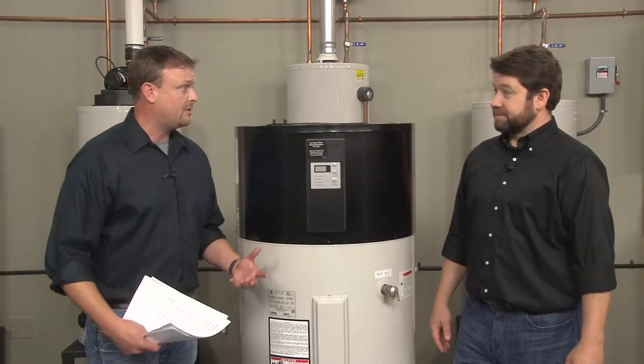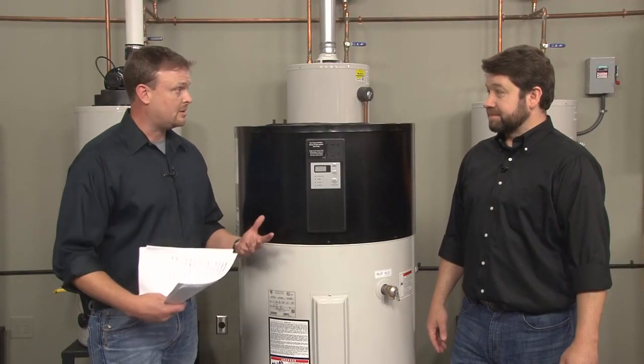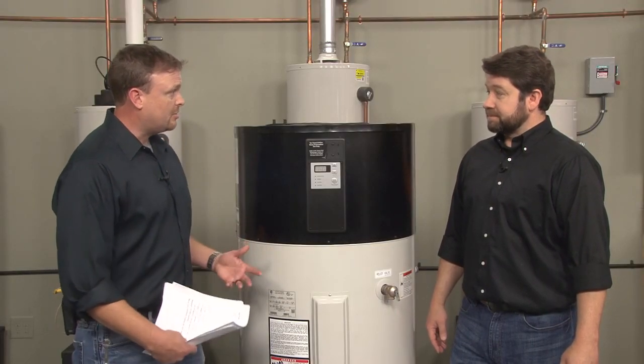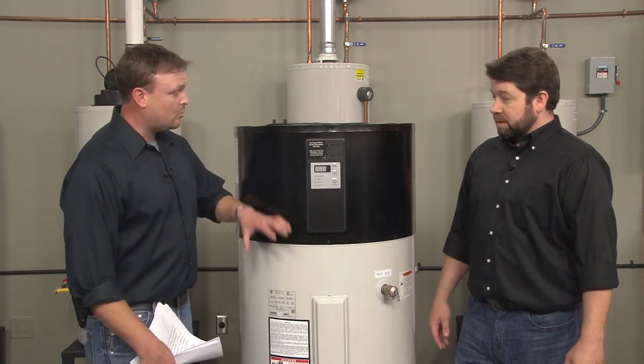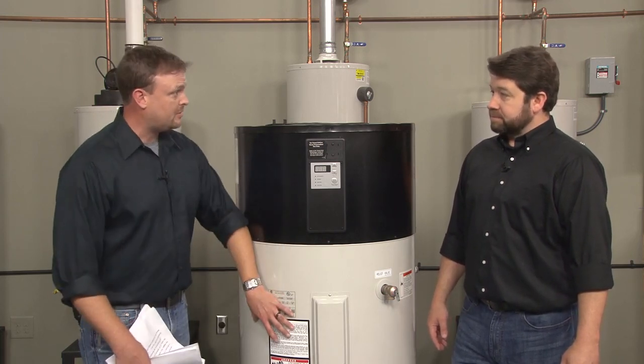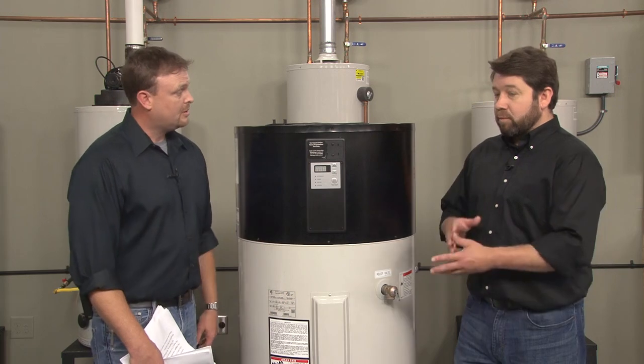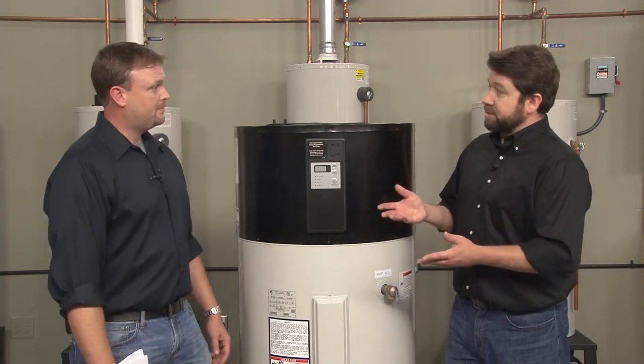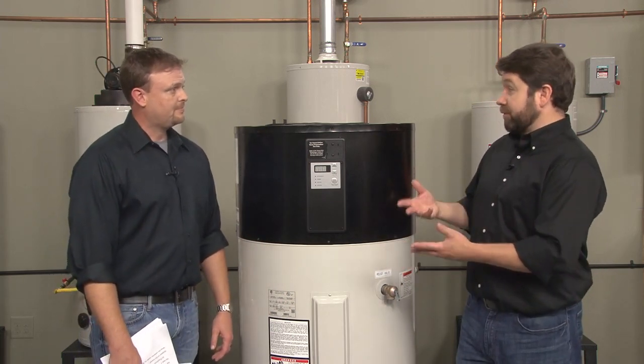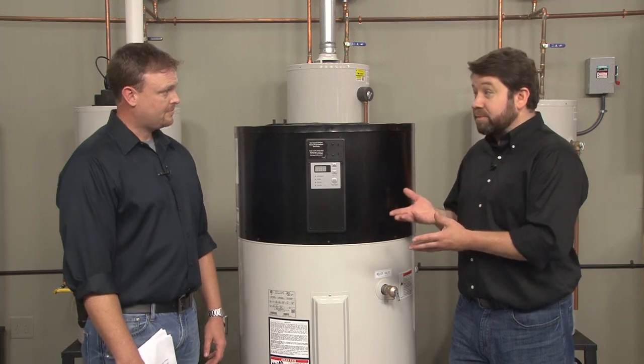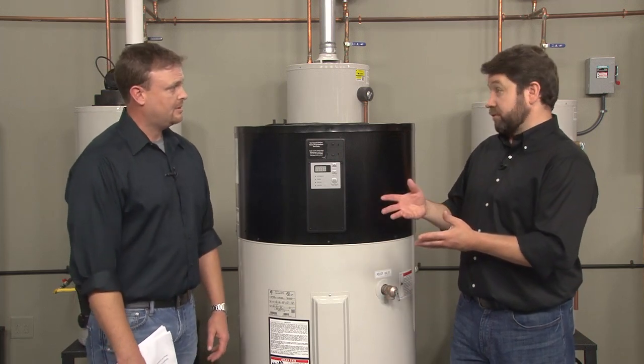So if you're in a situation such as family over during the holidays, you can run into needing more water, and it will actually use the heat pump and the electric elements in hybrid mode. If we're marginally over what we'd normally see, this is a good feature that gives you that hot water. It sacrifices a little efficiency by bringing the elements on, but gives you hot water when you need it.